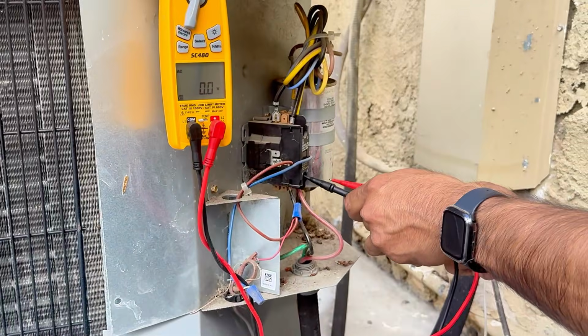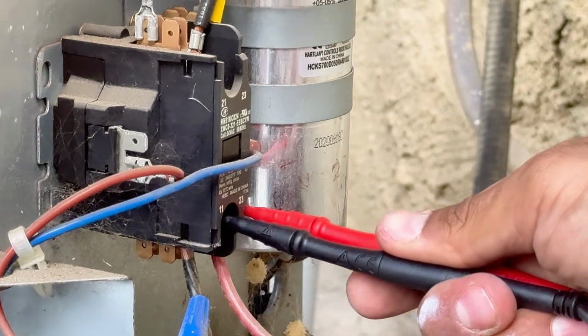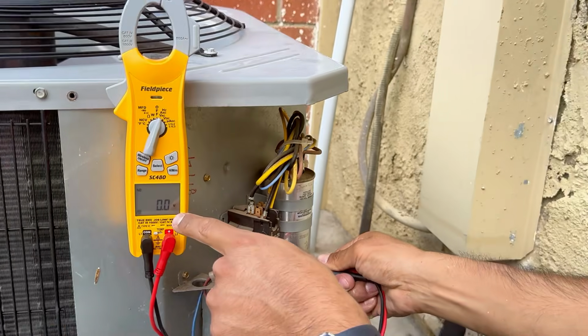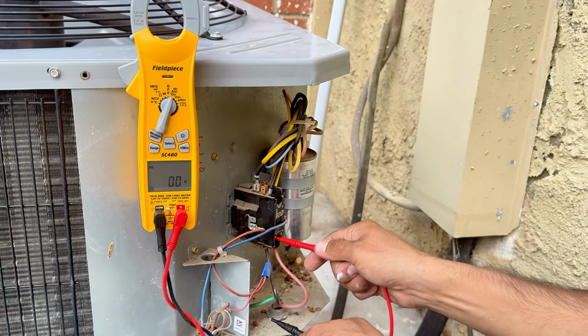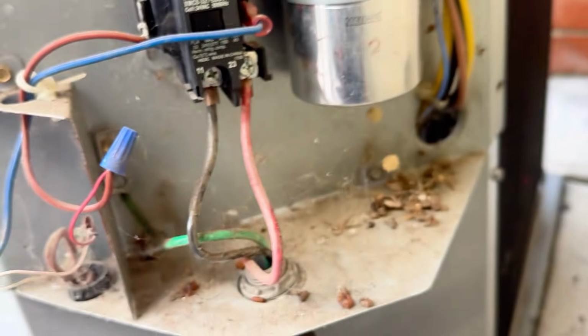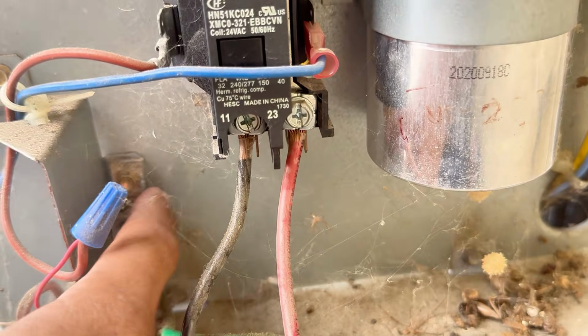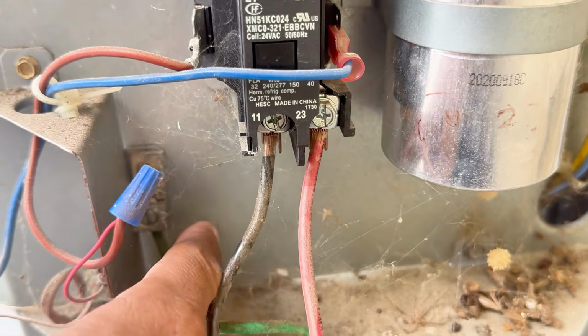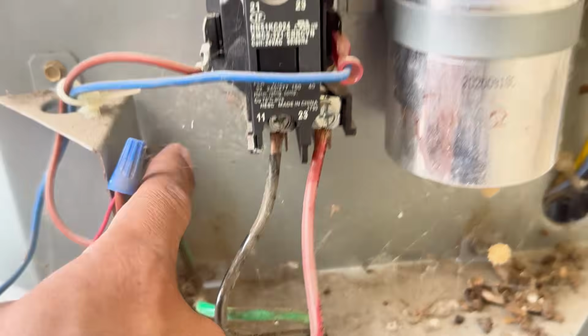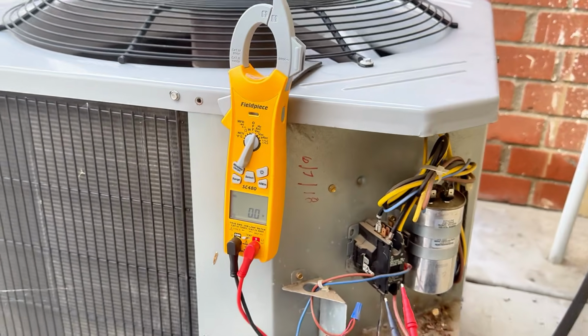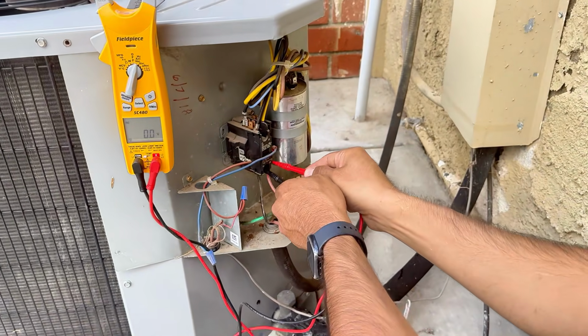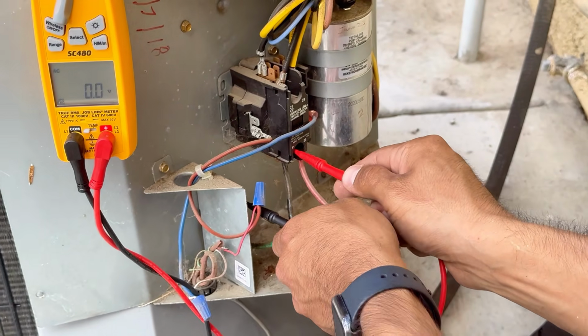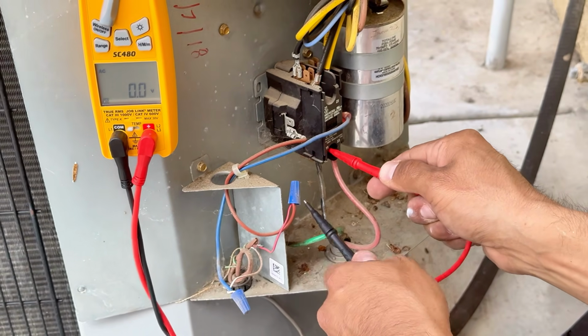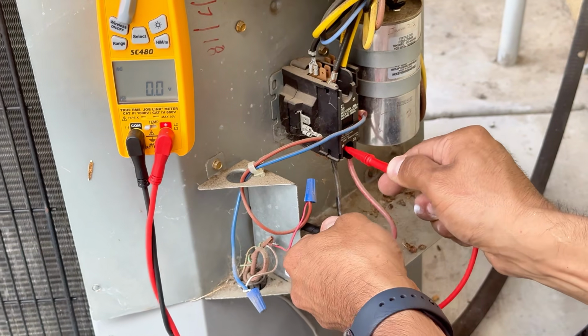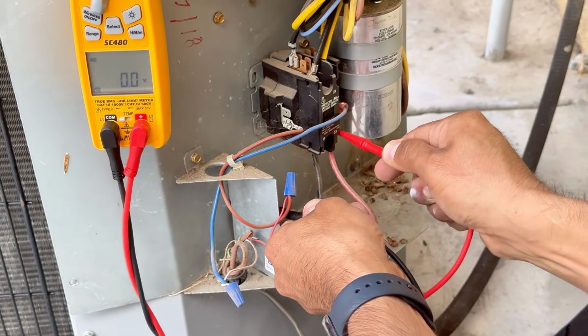I'm gonna go ahead and check this part here and that part there, line one and line two. You see, I have 0 volts. Then I'm gonna check line one and then ground, and I'll show you guys. Let me show you right here. You see that ground? Because it's grounded to this, everything's grounded, so I don't necessarily have to touch that lug there, I can touch anything. So that was, I should not be getting 240, and I'm not. Between this one and the ground, if there was power I would get 120, but I should be getting zero. Zero, and right here, zero.